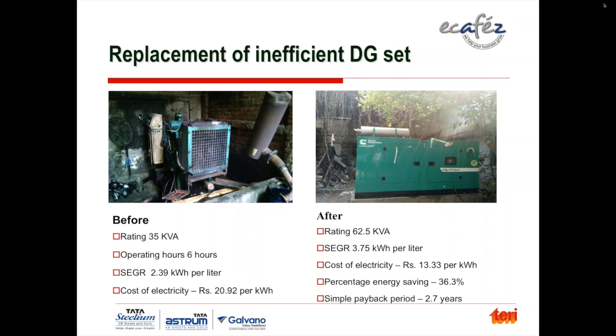As you can see, the condition of the DG set was very poor. This was the rating, 35 kVA, operating 6 hours per day, essentially in UP, where electricity is in short supply. And SEGR, the specific energy consumption, was 2.39 units of electricity per liter, 2.39.